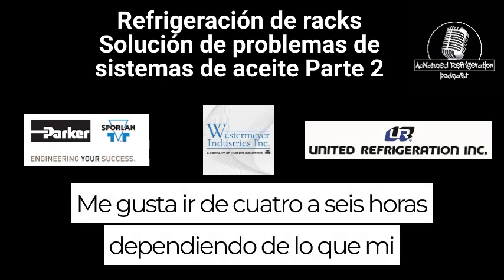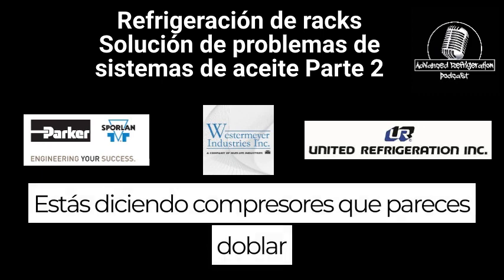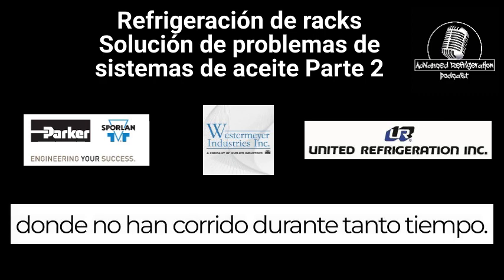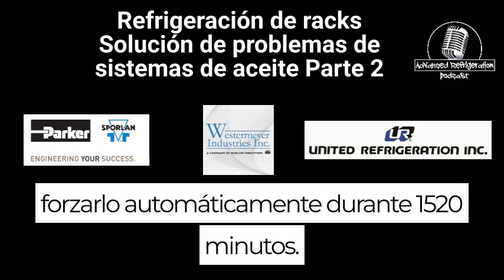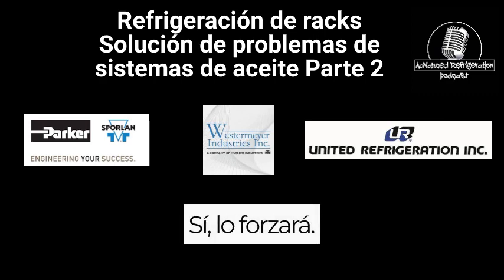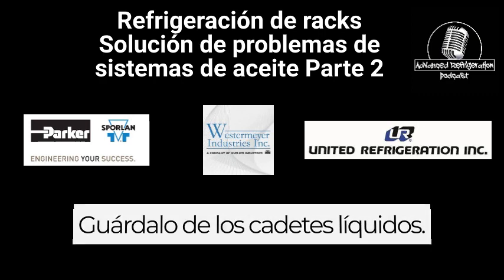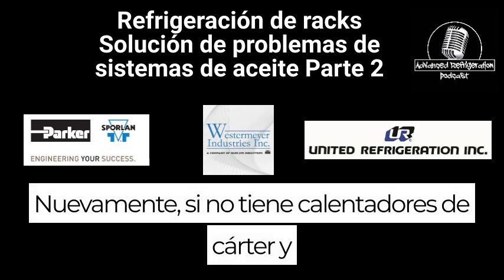I like to go 4 to 6 hours, depending on what my load is, to try to circulate. So every 4 to 6 hours, for the compressors that haven't run for that long, the controller will automatically force them on for 15, 20 minutes. Is that correct? Yep. It'll force it on, get some of that oil moving, get the compressor warmed up, keep it from liquid condensing in it if you don't have crankcase heaters, and it'll just get the oil out of it. I've had great success with only that.